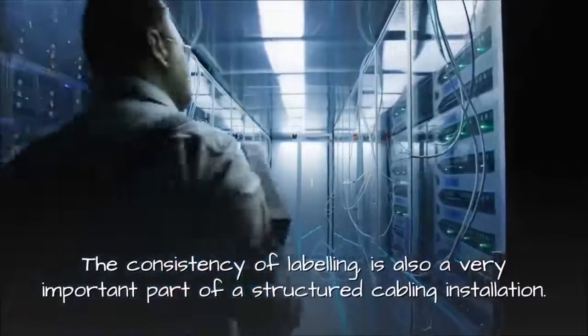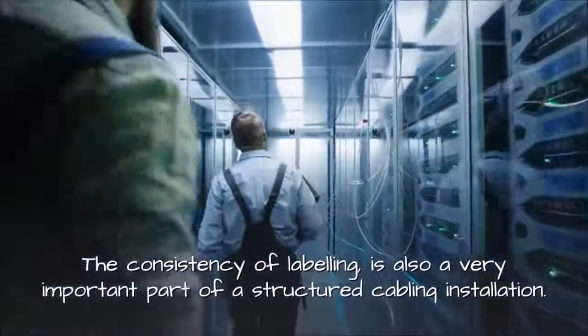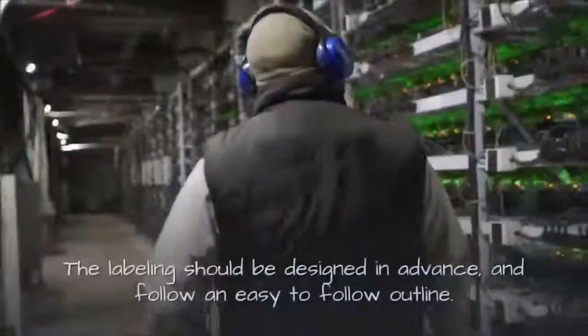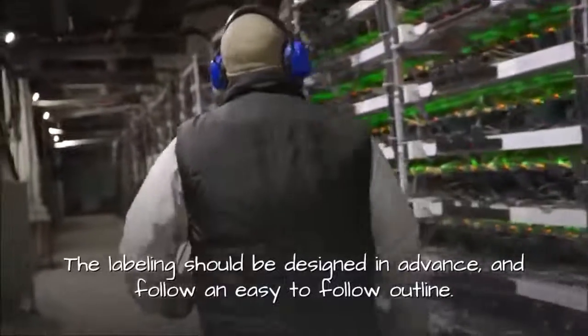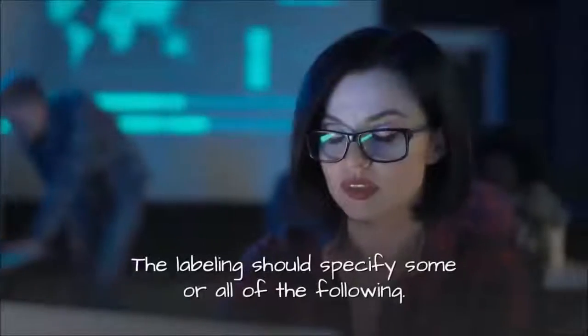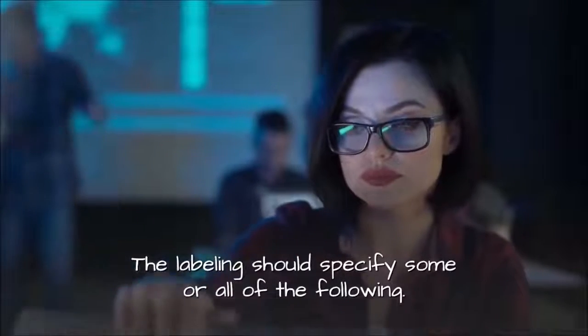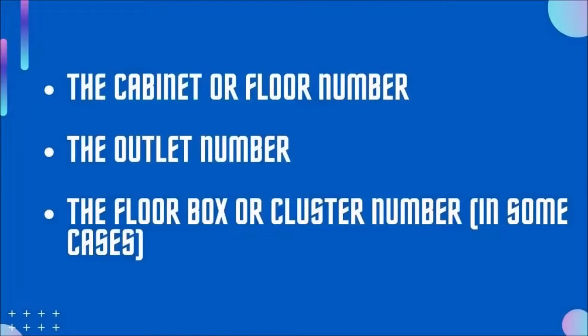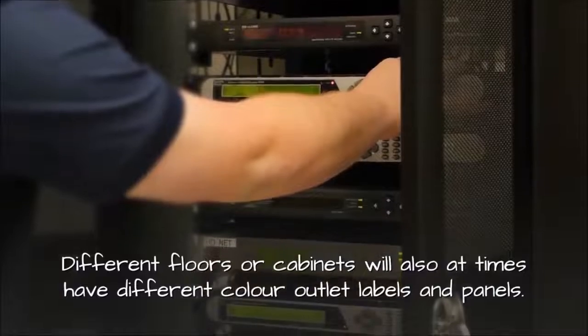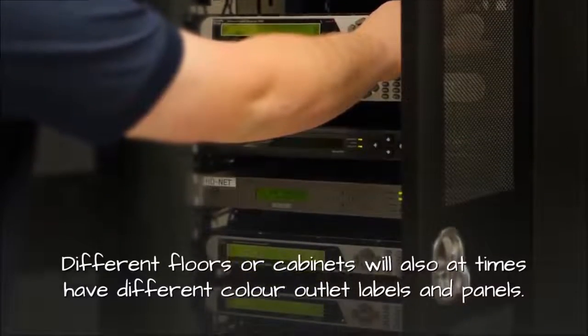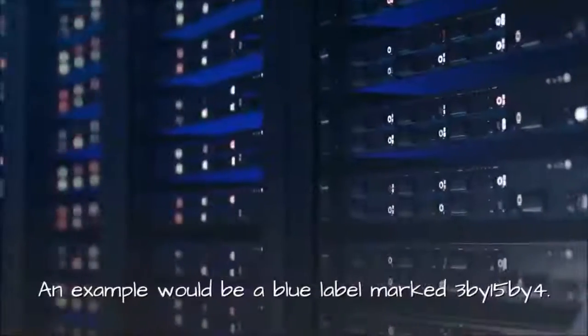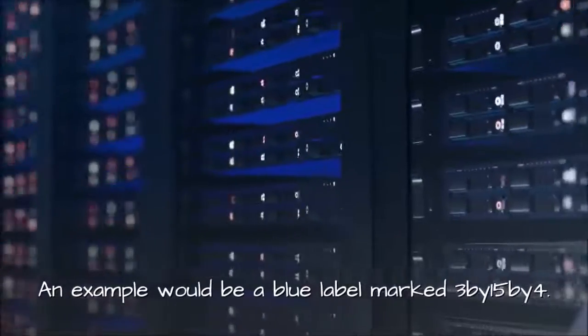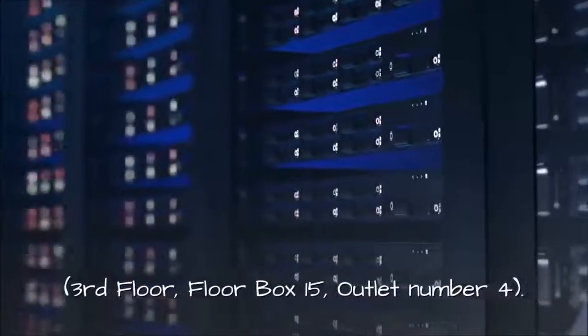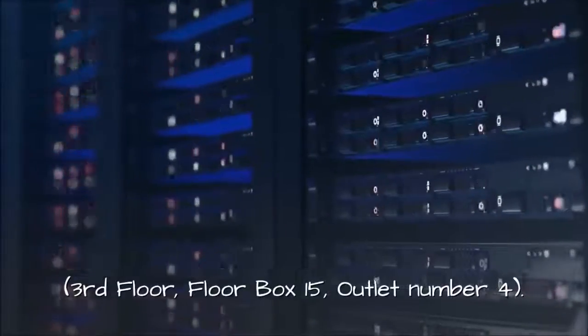Structured cabling labeling. The consistency of labeling is also a very important part of a structured cabling installation. The labeling should be designed in advance and follow an easy-to-follow outline. The labeling should specify some or all of the following: the cabinet or floor number, the outlet number, the floor box or cluster number, in some cases. Different floors or cabinets will also at times have different color outlet labels and panels. An example would be a blue label marked 3 by 15 by 4. Third floor, floor box 15, outlet number 4.